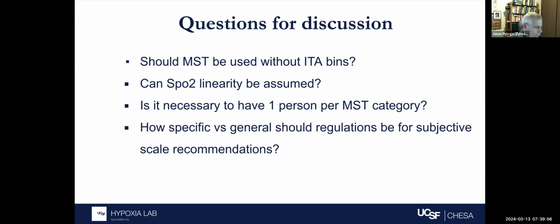Sure. I would like to understand, and maybe I just missed an earlier meeting on this, what question we're actually trying to answer. When we say, should MST be used with ITA bins or not, that question assumes a whole bunch of other things, and I don't know what those assumptions are. If we're trying to find out, for example, the effects of pigmentation on pulse oximeters in FDA-defined calibration or verification studies, then making measurements at the forehead is potentially not meaningful because the pigmentation level at the forehead might not match the pigmentation level at the sensor site. It'd be great to do it at the forehead if we're using a forehead sensor.